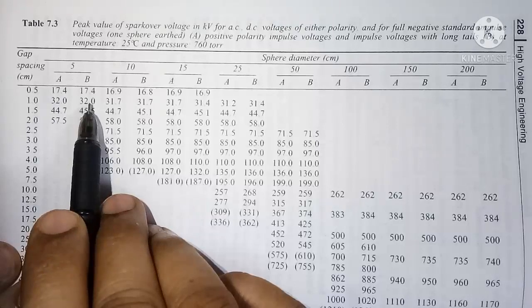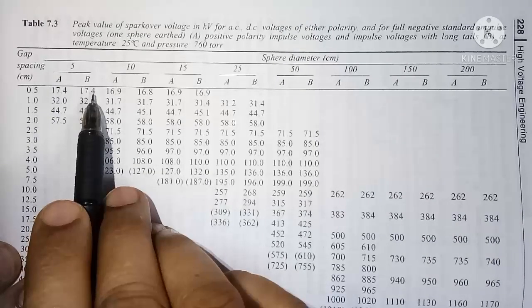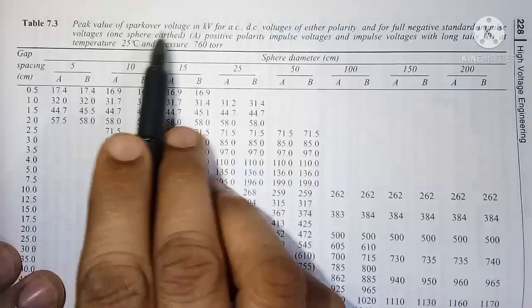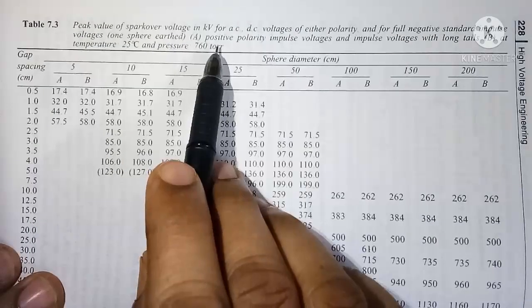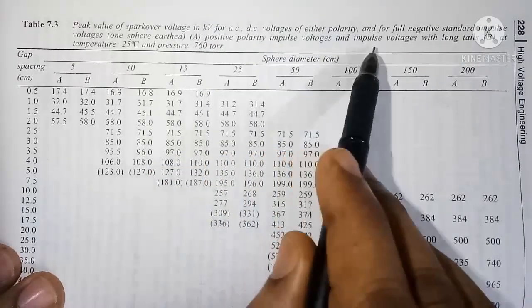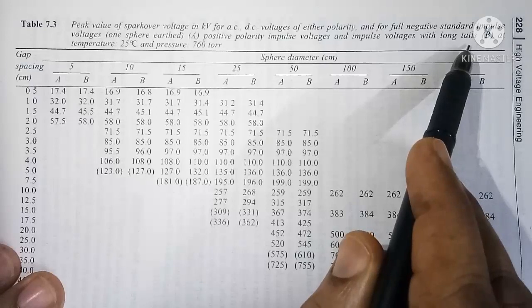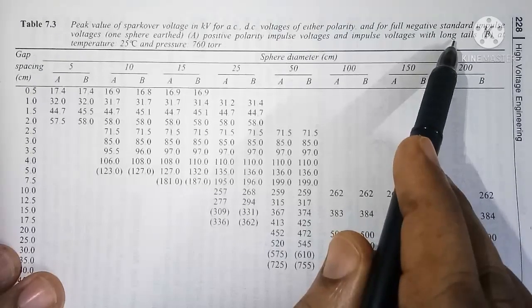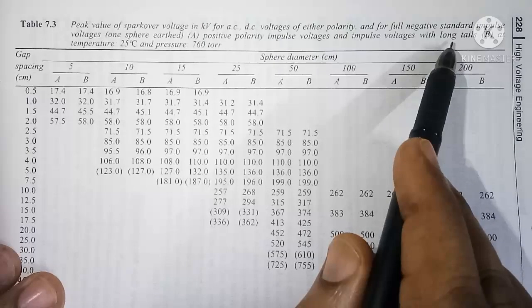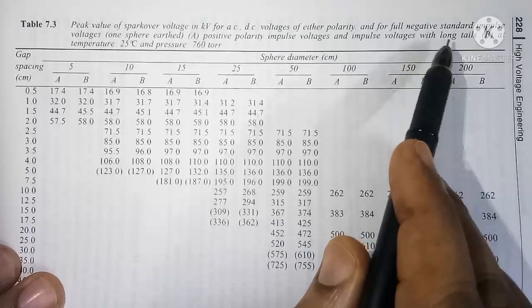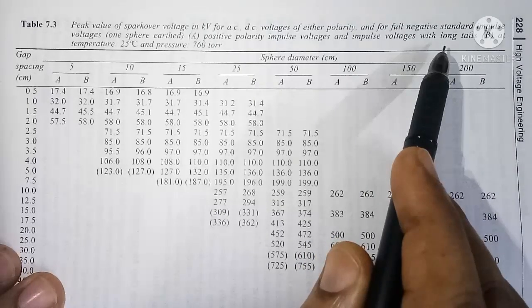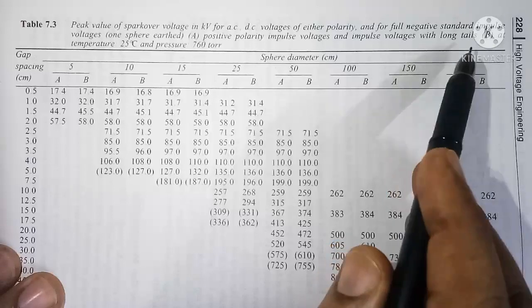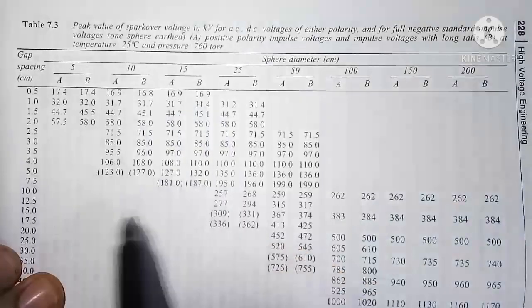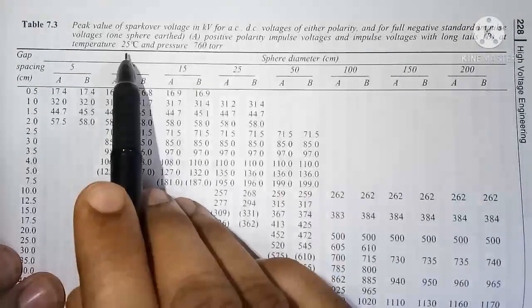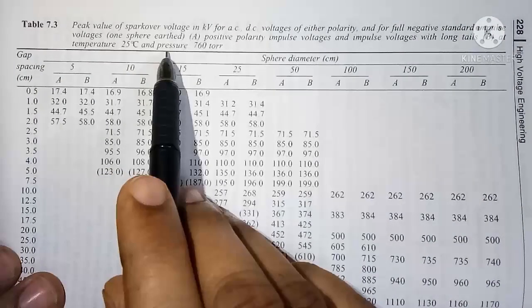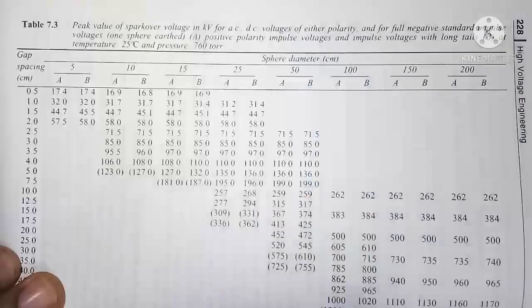Also, if you look in column B, 17.4 tells us the peak value of spark over voltage in kV for positive polarity impulse voltages and impulse voltages with long tails. Long tails means the tail length of the impulse voltage should be more than 5 microseconds, and these values are valid only for a temperature of 25 degrees Celsius and pressure 760 torr.